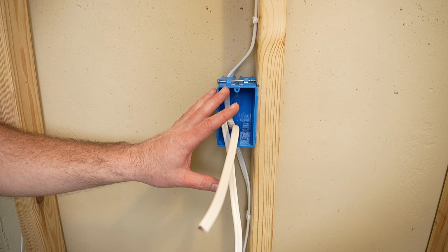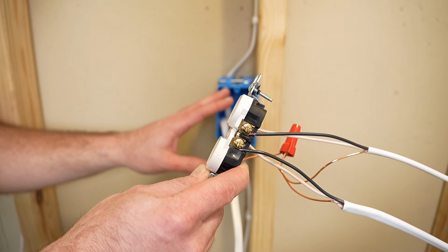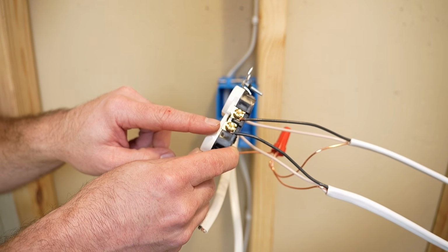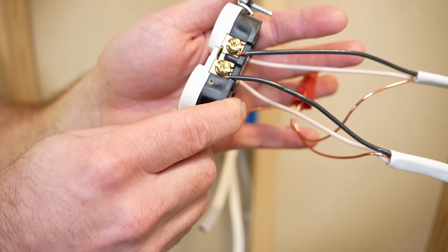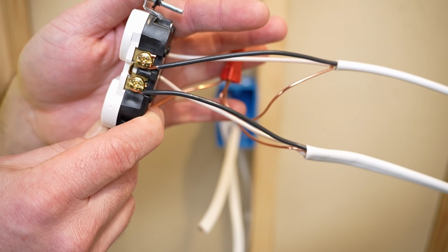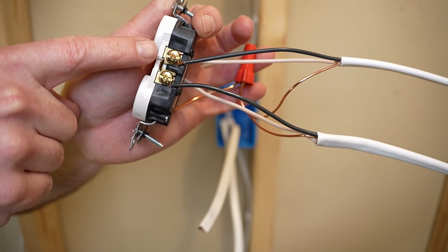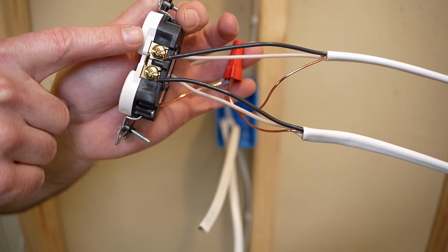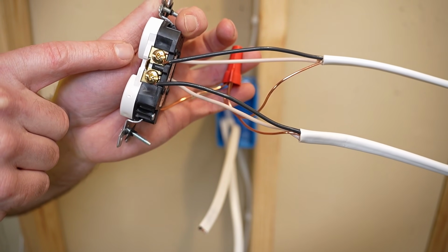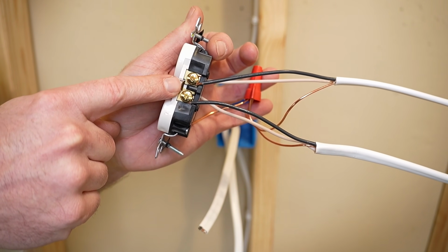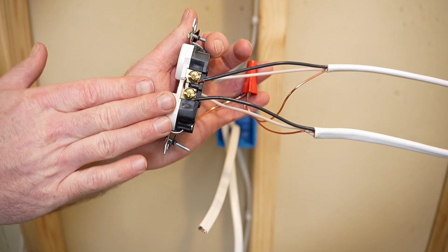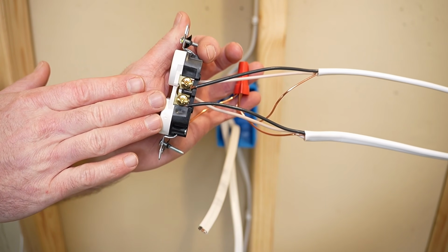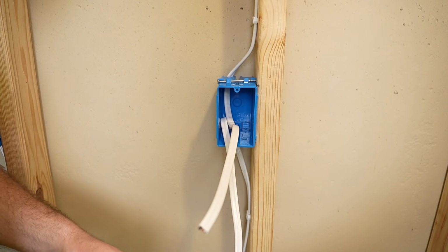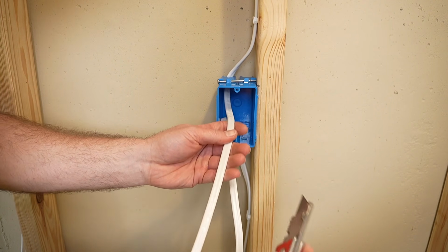On this last box, we're only going to be pigtailing the ground, because on this box we're going to be installing the receptacle this way. So there's not going to be any pigtails on the hot and neutral. We're actually just going to use the terminal screws on the device itself as the splice. Again, there is nothing in the code that says you can't do it. This is not my preferred method though. I very much prefer the pigtail method. So just like with the previous boxes, we need to strip out our cable.